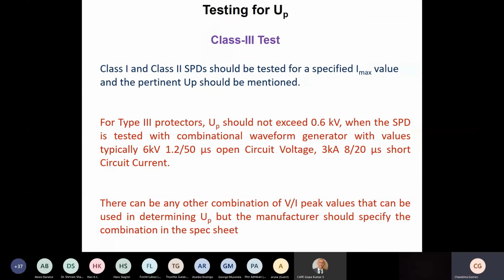Then for the type 3 SPDs, when you apply a voltage of 6 kV and a current of 3 kiloamperes, with the wave shape at 1.2/50 and 8/20, then the output voltage should be 0.6 kV. Then for all other SPDs also you can test it, but make sure that when a manufacturer says that my 50 kiloampere IIMP or IMAX SPD has a 0.7 or 0.8 kV UP value, this is very, very impractical. Most often what they may be telling is that their nominal current handling capacity is 50 kiloamperes, but they have tested it for the 6 kV 3 kiloampere waveform, but they try to imply that when 50 kiloamperes is applied, the output voltage is 0.7 or 0.8 kV, which is not feasible.